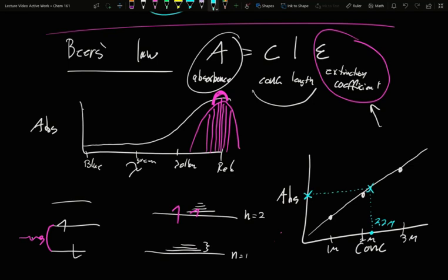But you can get an equation for that line because there's a slope. This is a y equals mx plus b. B is our intercept. X is our concentration. M is the slope. This is what the graph is good for giving us. It tells us, for each increase in concentration, what increase in absorbance do I expect? And Y is our absorbance. You can rearrange this. If you've done it for a calibration curve, now you can put in any Y value and solve for the X value.